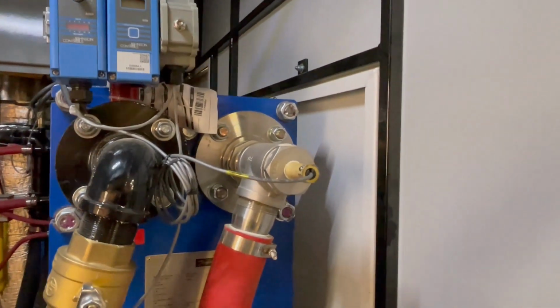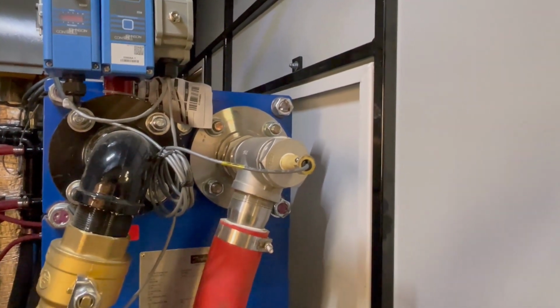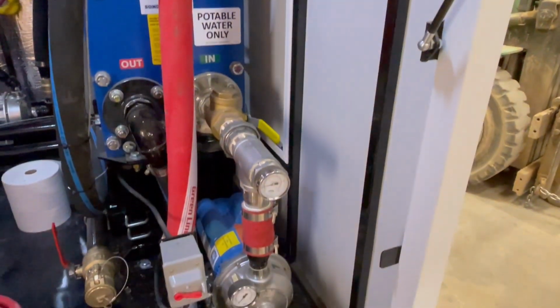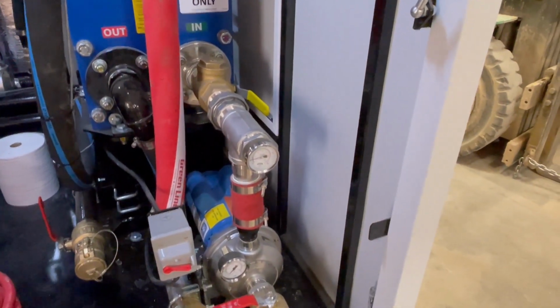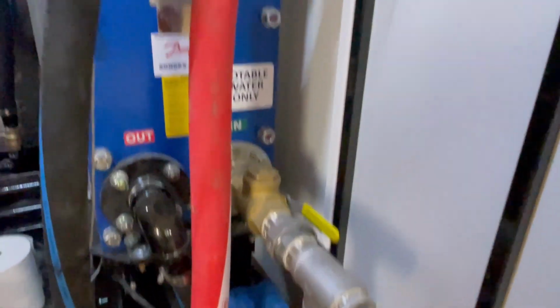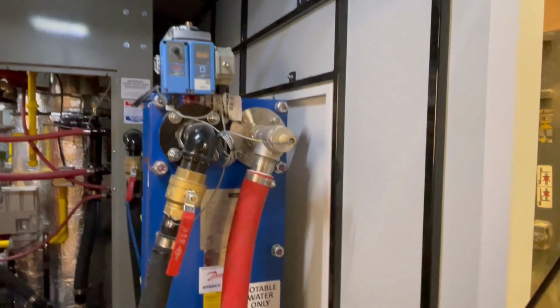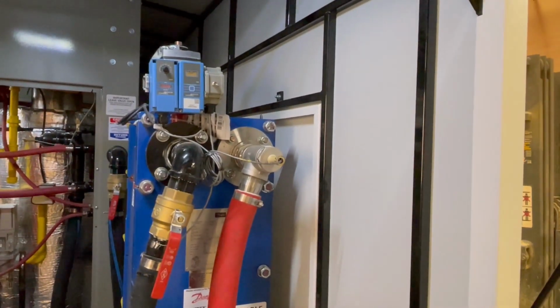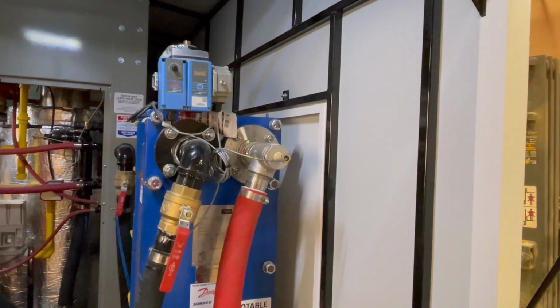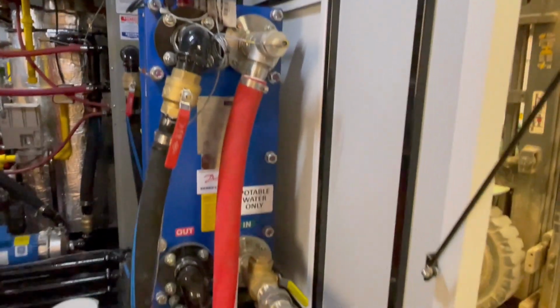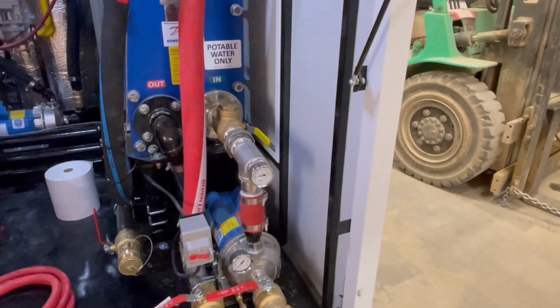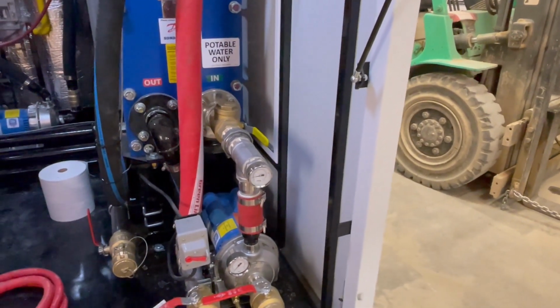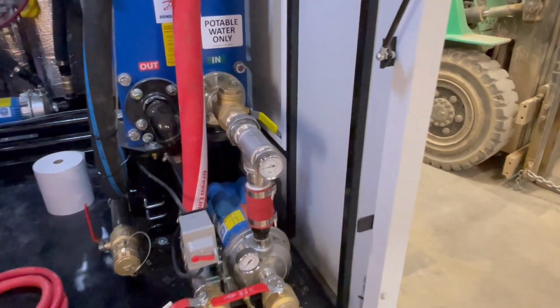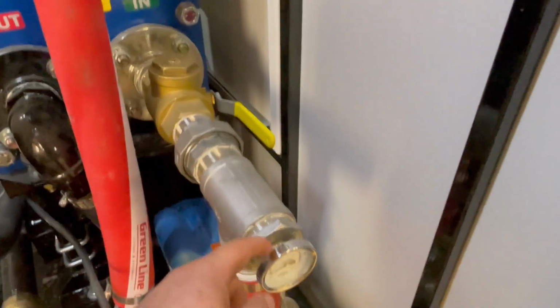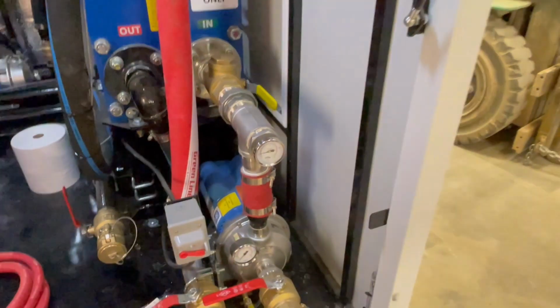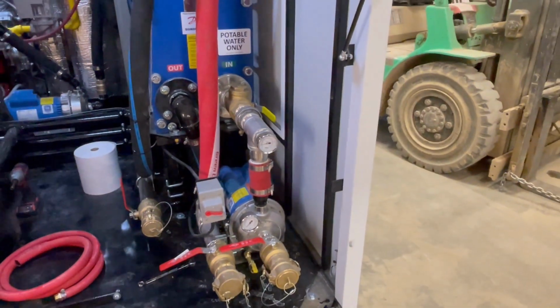The temperature probe for this controller is currently in the water outlet to measure the water temperature going out of the plate. This is beneficial for on-demand water purposes where the water inlet is always cold, like city water. You can move the sensor and swap positions with the gauge on the water inlet. Then it will measure the water temperature into the plate. This is beneficial for setups where the system temperature needs to be raised, like a large tank.